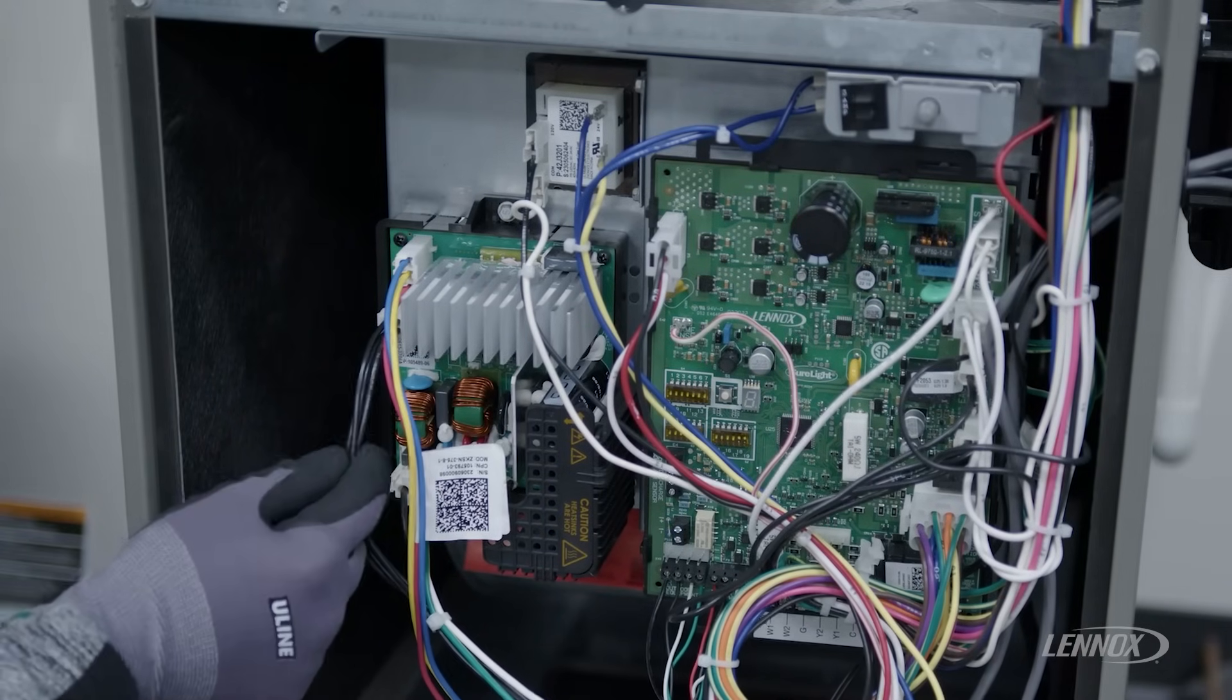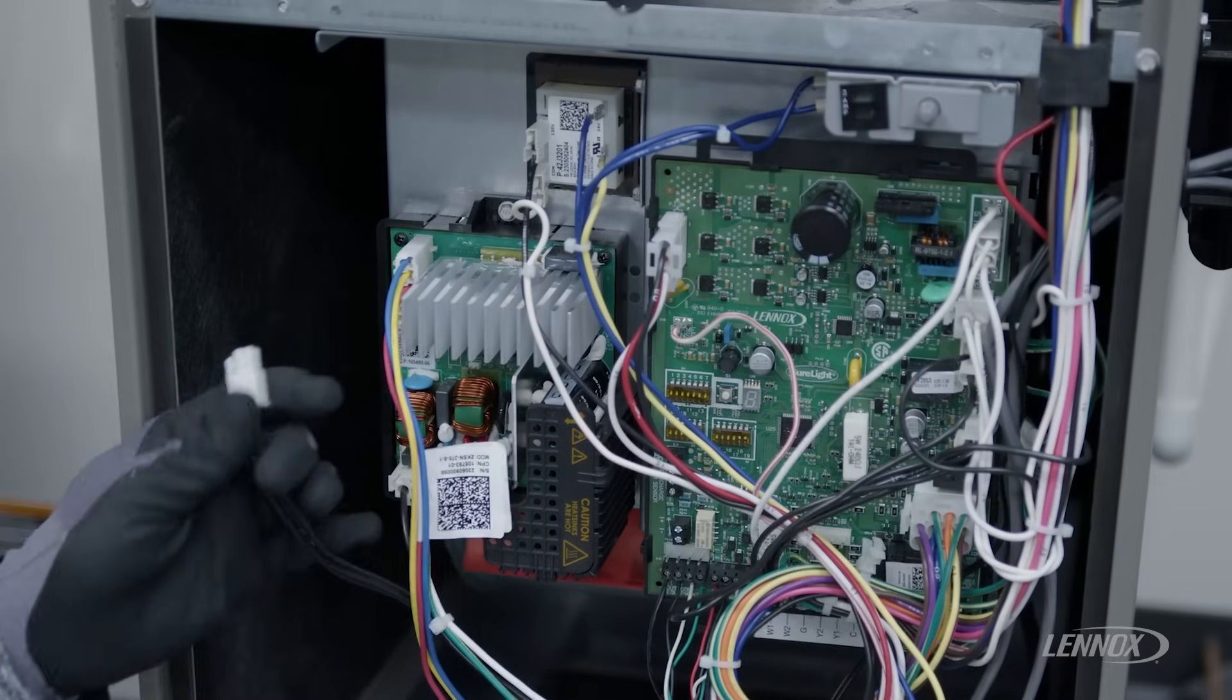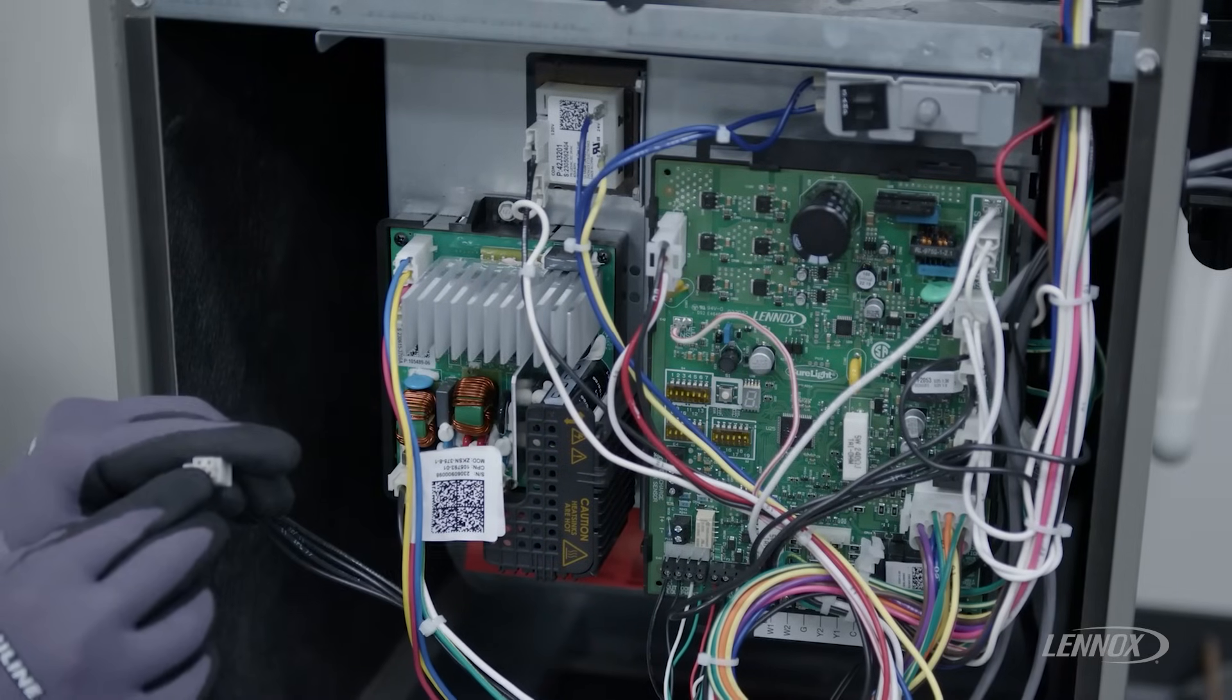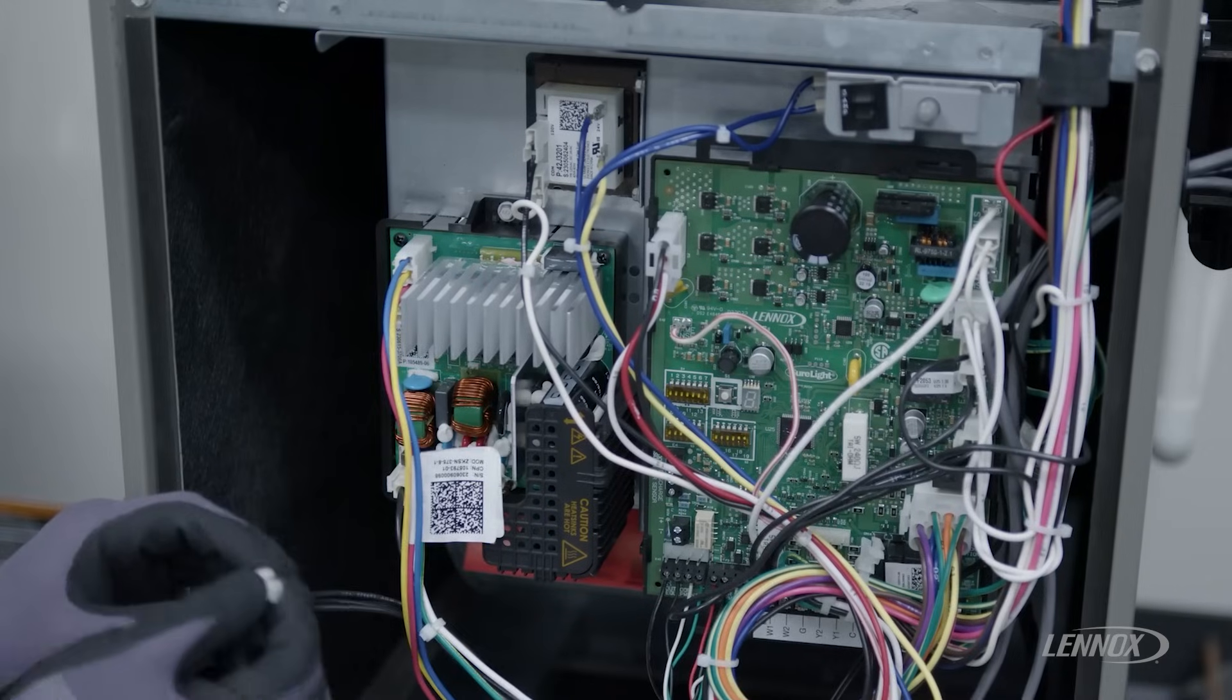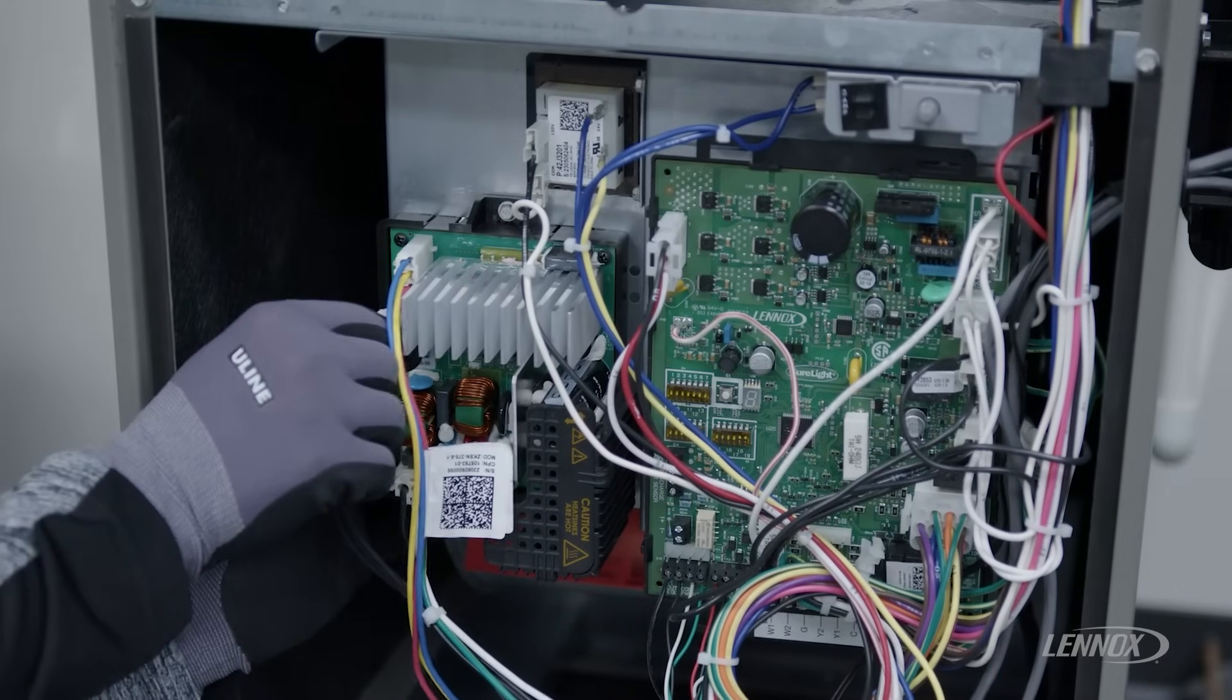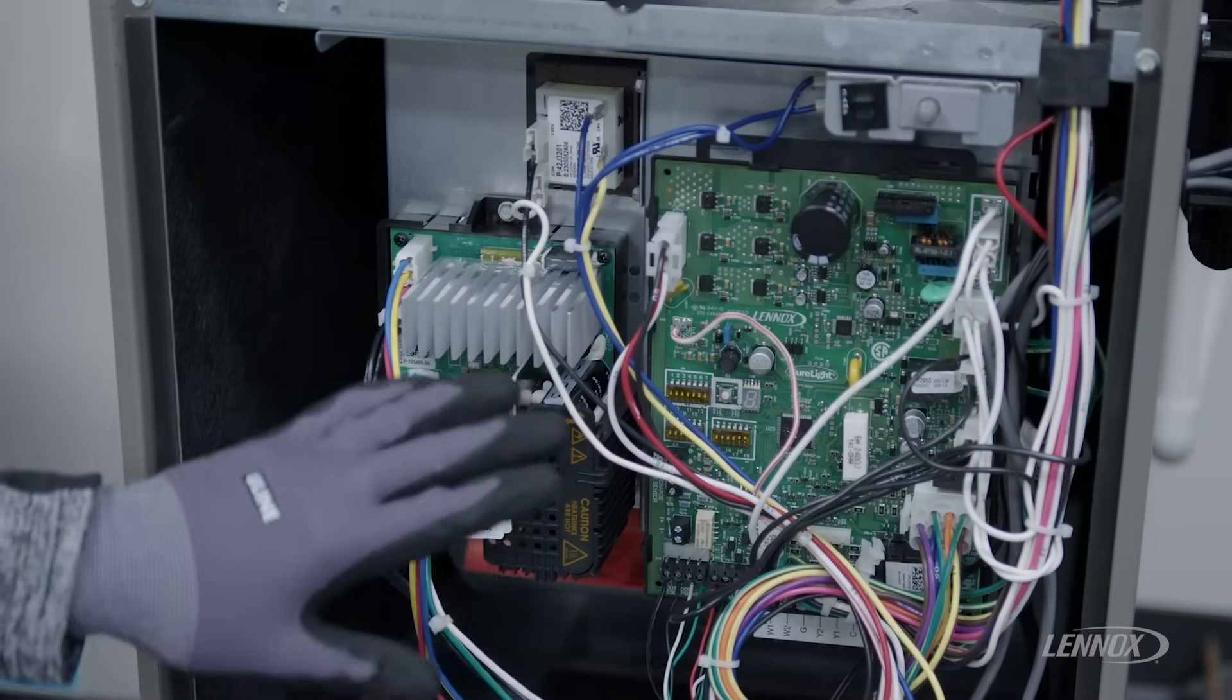I would take it out, inspect our terminals here, make sure it's free of corrosion, debris, or any loose wires in the back of the plug. I would then plug it back in, and I would rinse and repeat that check on the control side.